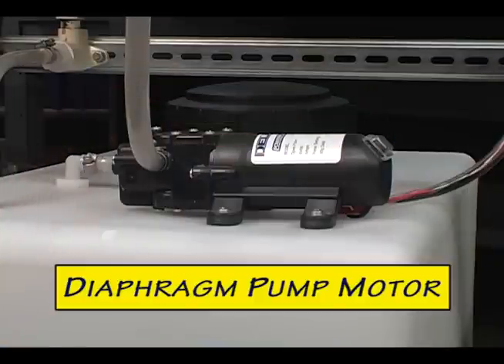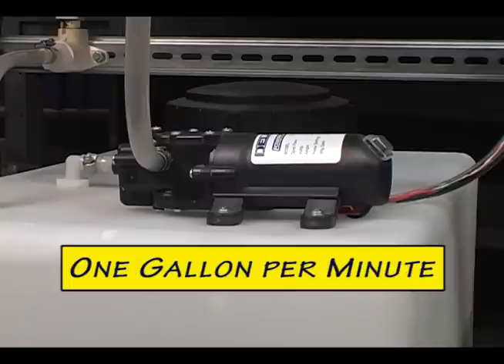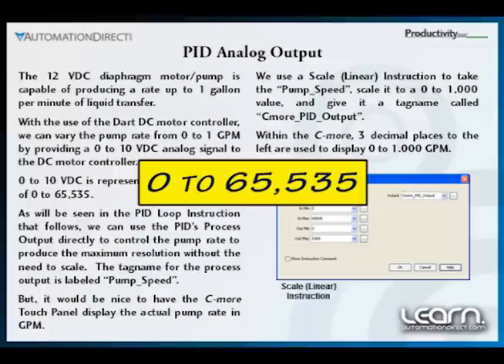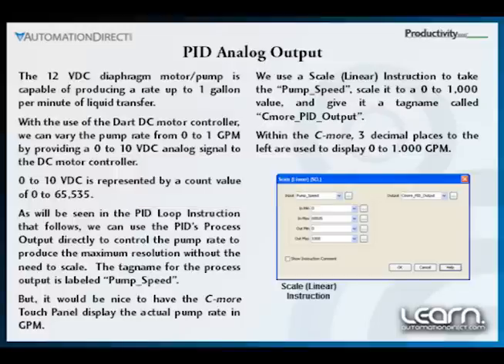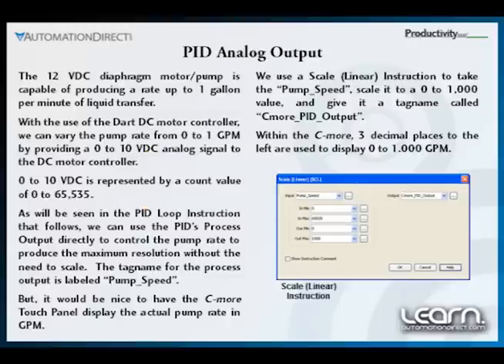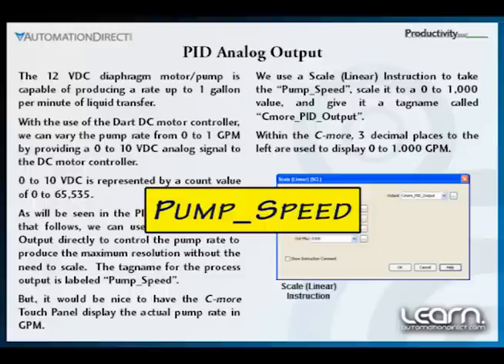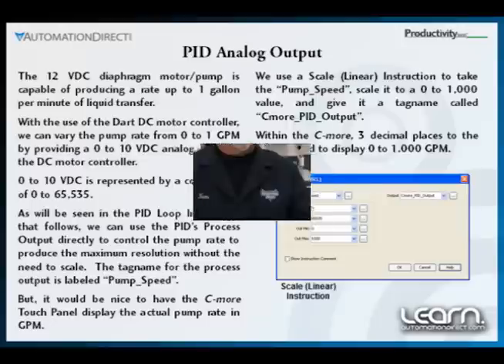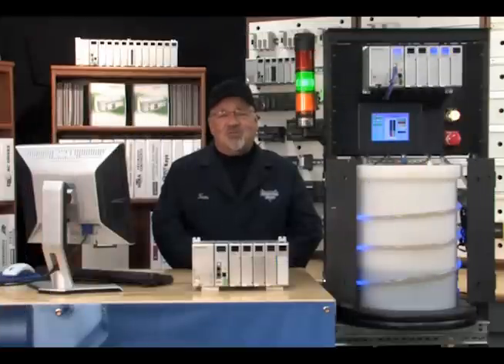The diaphragm pump is capable of producing a flow rate up to 1 gallon per minute. The analog output module uses a 32-bit integer value with a range of 0 to 65,535 to produce the 0 to 10 volt DC signal. We will use the PID's process output directly to control the pump rate, giving us maximum resolution without the need to scale. We will create a tag name called pump_speed used as the PID loop's process output that directly controls the analog output module's channel 1, which is wired directly to the DART DC motor controller's 0 to 10 volt DC analog input.